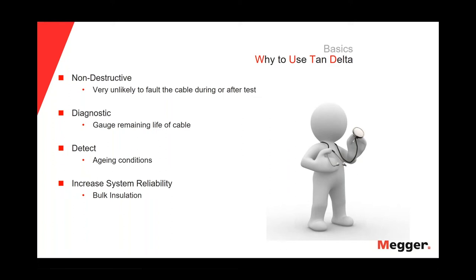And it's a diagnostic tool to measure the remaining life of the cable. The idea is to detect the aging conditions in the insulation of the cable. Of course, we use the tan delta to increase the system reliability, okay? That is the reason why we use the tan delta.